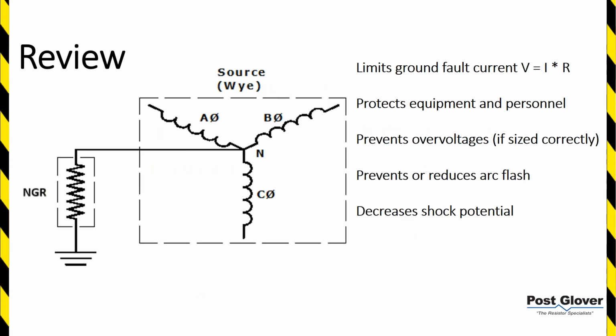So when we talk about resistance ground, all we're talking about is a resistor between the neutral and the ground, like you see here, in series. So you have the neutral connection, XO point here, of your transformer, of your generator, going in through the resistor to ground. What this does is essentially, the idea is this will be your only intentional ground path, and you have basically your current on the ground fault being forced through this resistor, impeding or choking the amount of current that can flow through it.